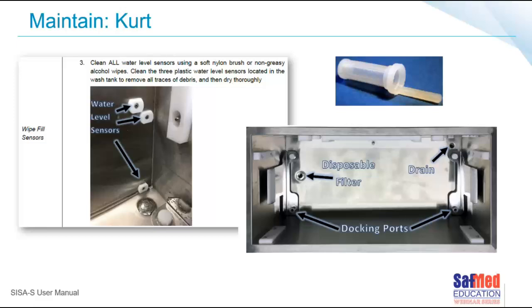And then, as you can see in the picture below, you'll find the drain and the docking ports. It's very important that you make sure these areas are kept clean and free from obstruction, lint, or any other debris. If the docking ports are clogged up, you're not going to get any water flowing and pressure flowing through your lumens if you're connected to the lower pipes. And if the drain is clogged up, the water won't drain out correctly, which will ultimately result in an aborted cycle at the end.